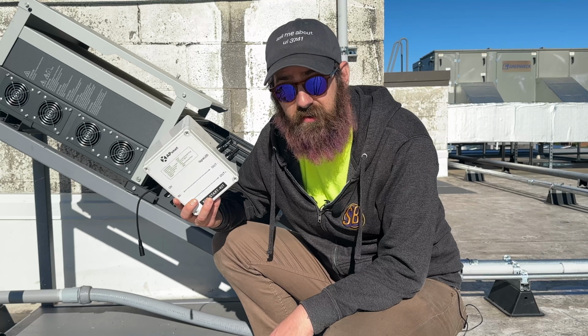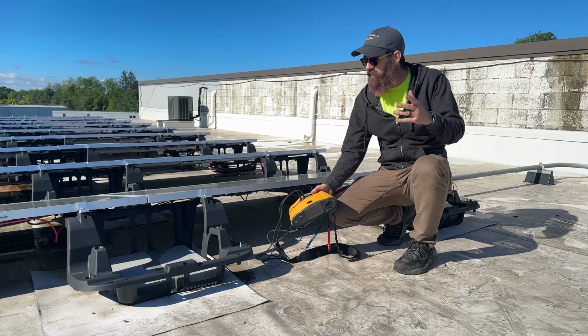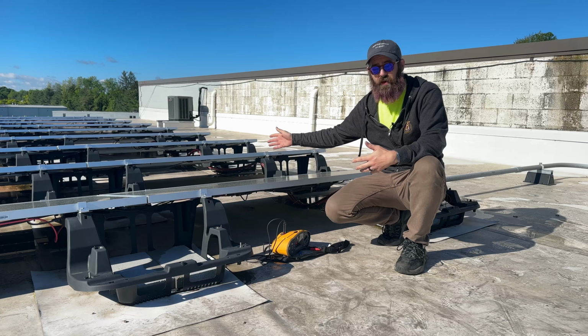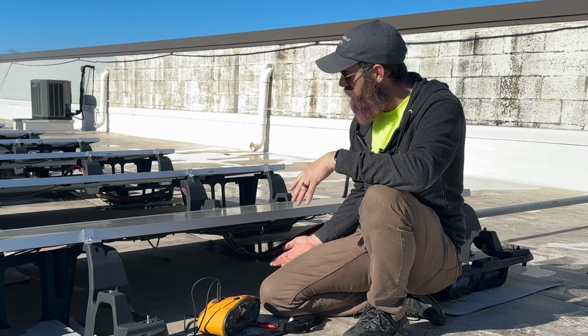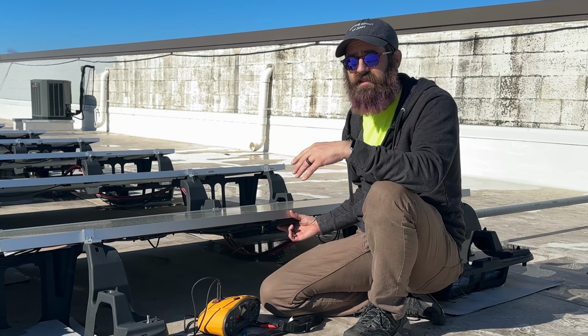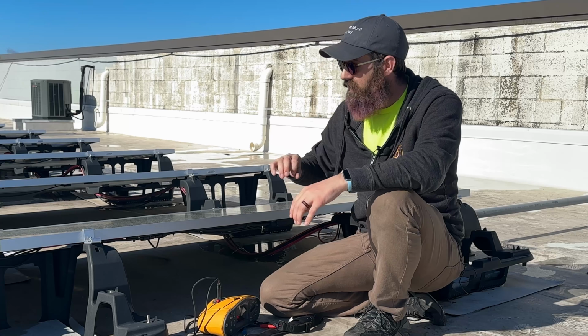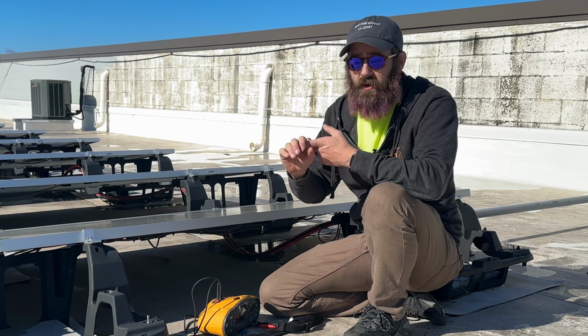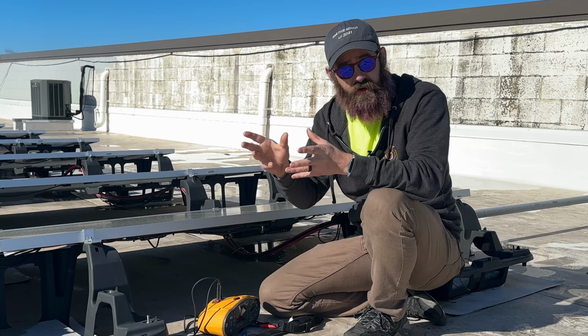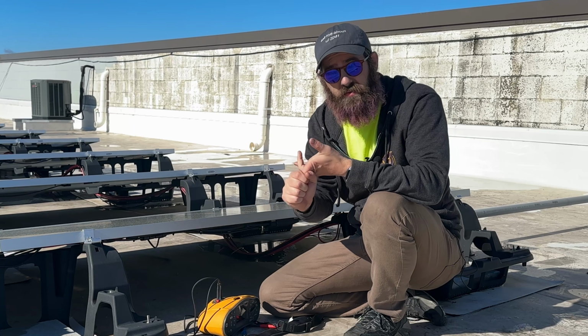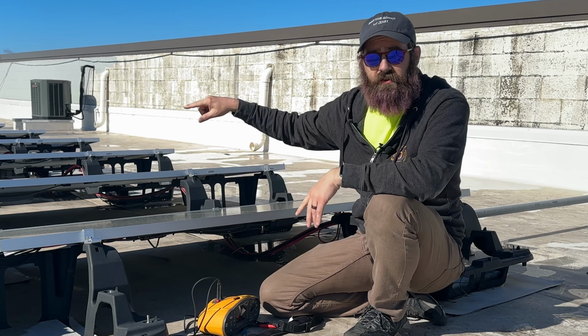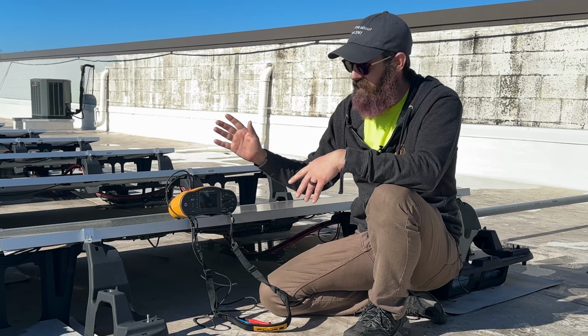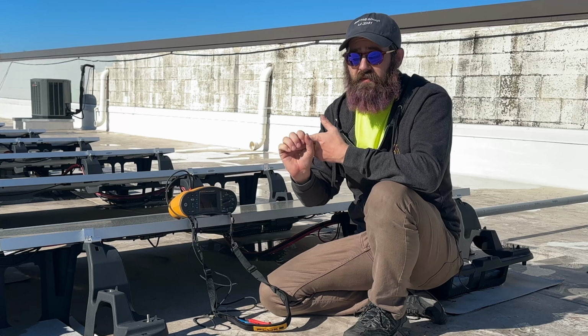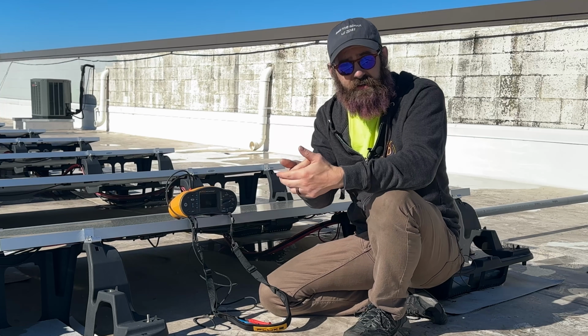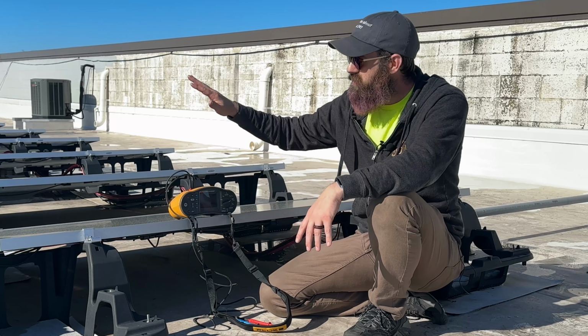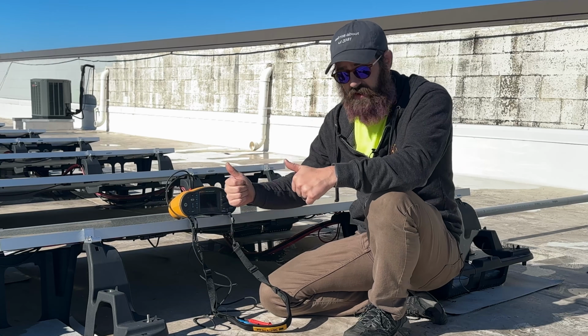But this, though, definitely should be possible. Why can't we just curve trace through a line of rapid shutdown devices? Well, in order to turn on every single one of these devices, they need to see a certain signal pulse going through the line. To do that, you need a transmitter and you need the circuit closed enough to allow that signal through. No curve tracer out there has that transmitter built in, nor does it have that pause after connecting the circuit to let the pulse travel through and turn on all the rapid shutdown devices.